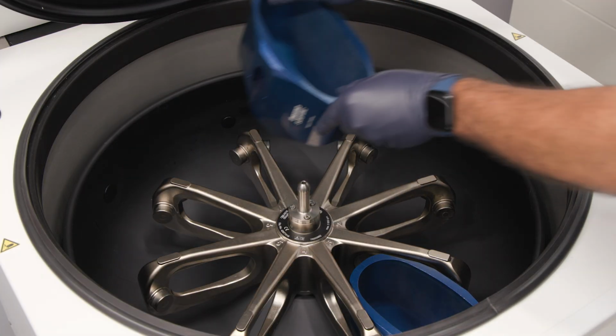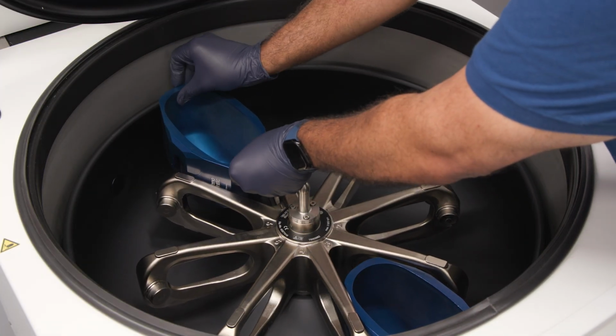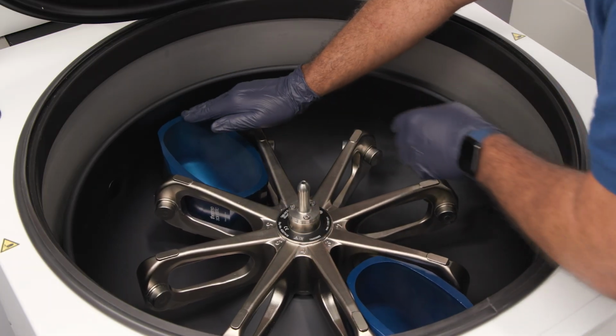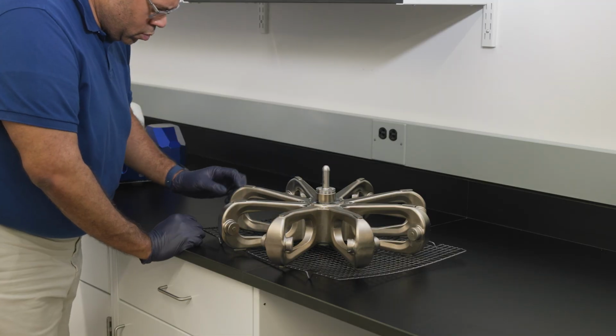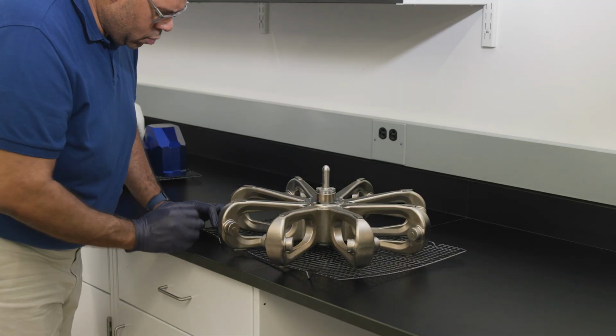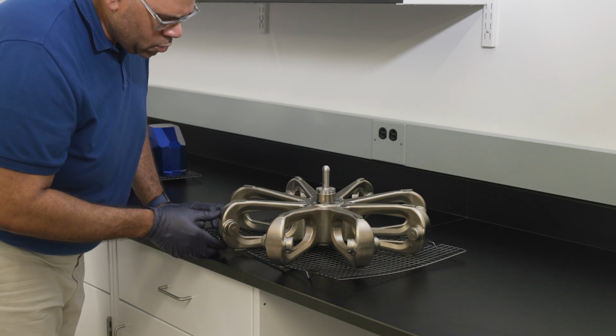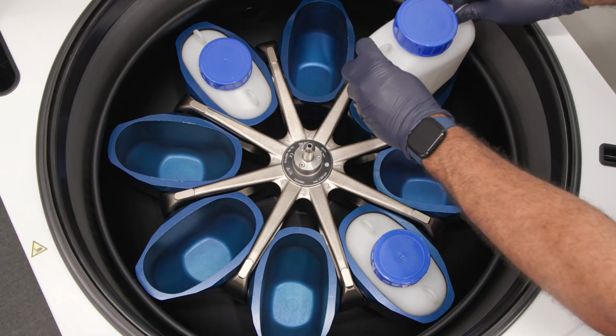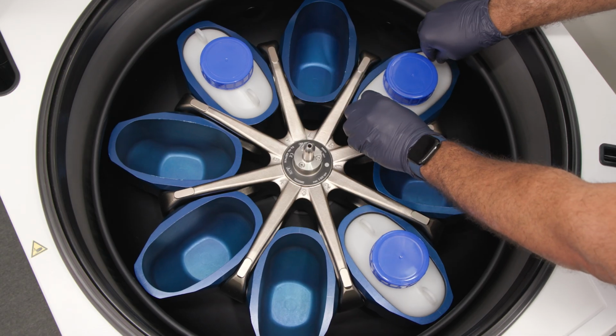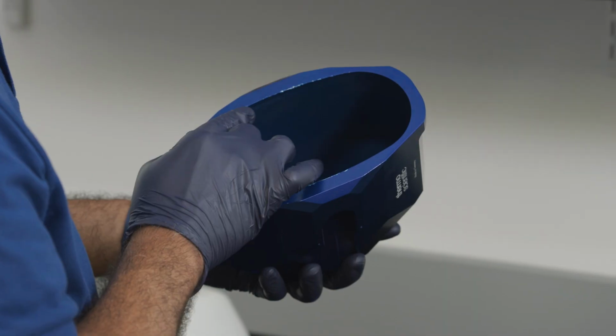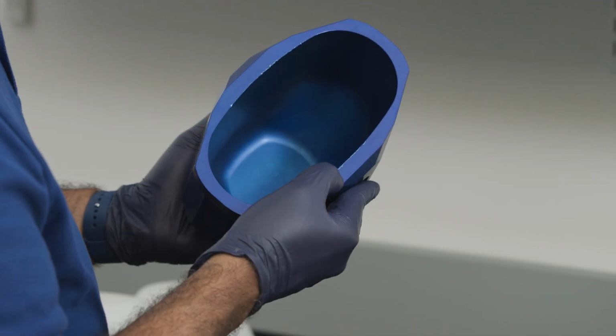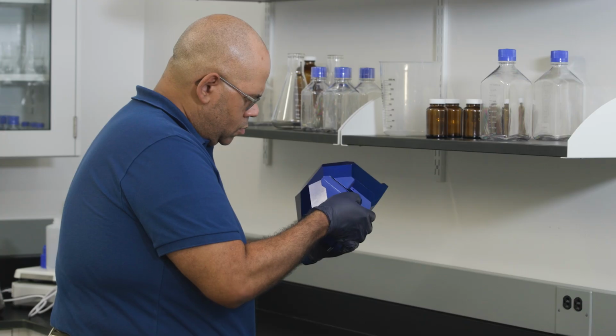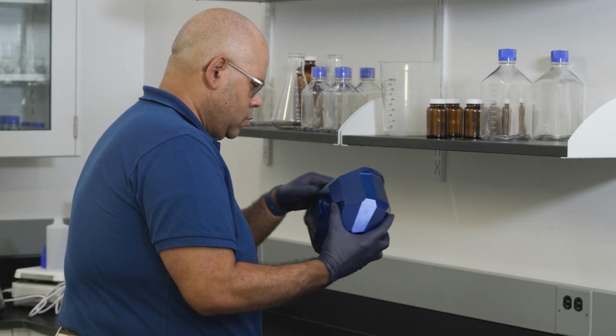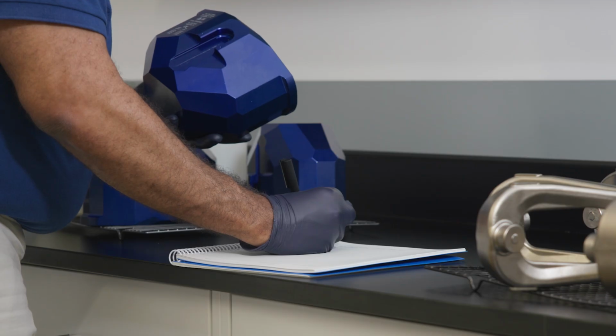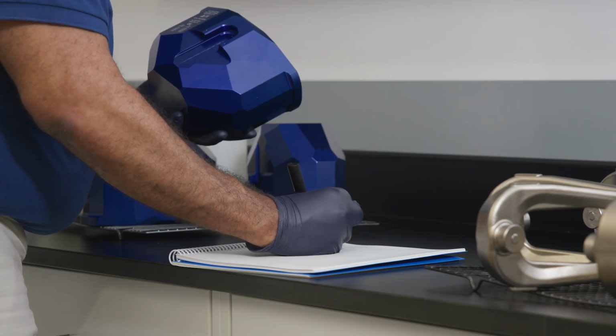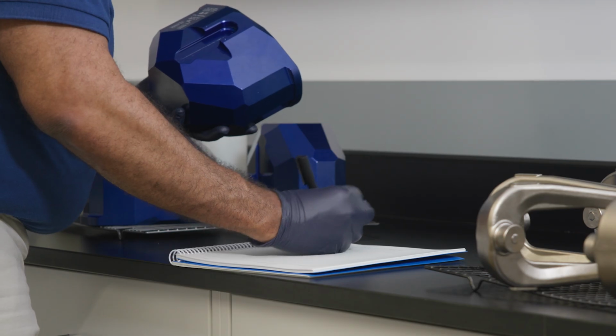Check that the rotor, buckets, and components are within their service life and number of cycles. Rotors and components should be inspected yearly as part of routine service to help ensure safety. Do not use any rotor or components if they show signs of damage. At this point, check that the protective coating is complete. It can be removed through wear and chemical attack and can lead to unseen corrosions. If the rotor or accessories are corroded, they must be removed from service immediately.